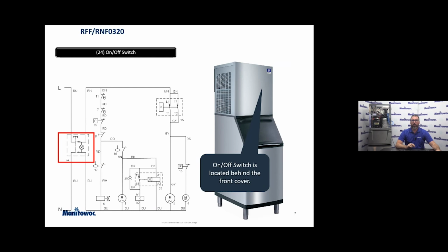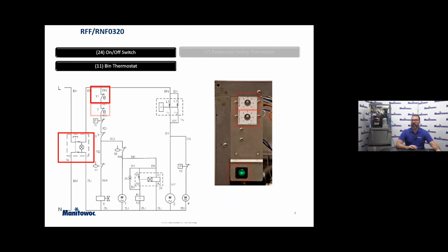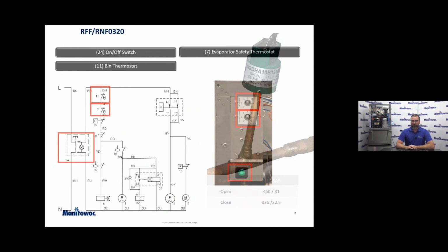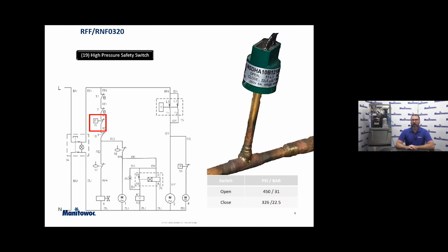So the 320 is going to be just like the undercounter 200 and 300 we just talked about earlier. We are going to bring our incoming power through that on-off switch. Our line wire or brown wire is going through a succession of different safeties. We got our, of course, bin thermostat safety. That's going to give us the bin level that we can set and choose. Our evaporator safety thermostat. Here we also have a high pressure safety switch, for if we do get into a condition where, say, the condenser fan motor fails, or we have a blockage in the system on the high side of the system, etc. If we get too high of a head pressure, of course, this safety is going to open. Now you can see some pressures there on the bottom of the screen, cut in and cut out.